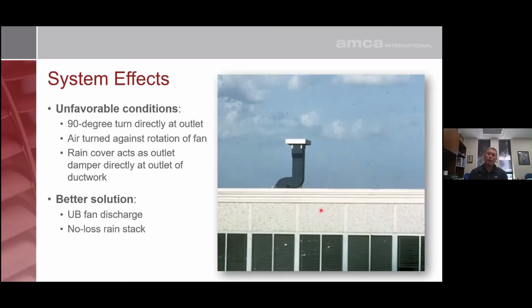Here we have another fan. This is on top of a federal building. Again, we have a top horizontal fan with a position C elbow this time. Air deadheads, has to get re-accelerated out. And we have a rain hood at the discharge of the fan. Air deadheads here, it has to get bent down 180 degrees. This fan is not going to perform as cataloged.